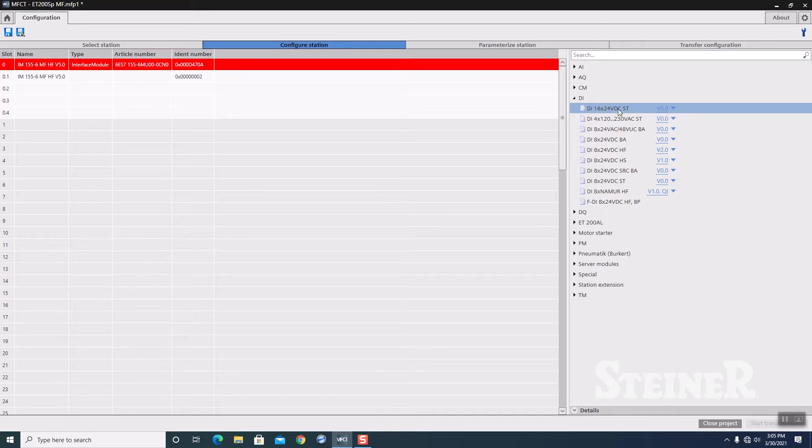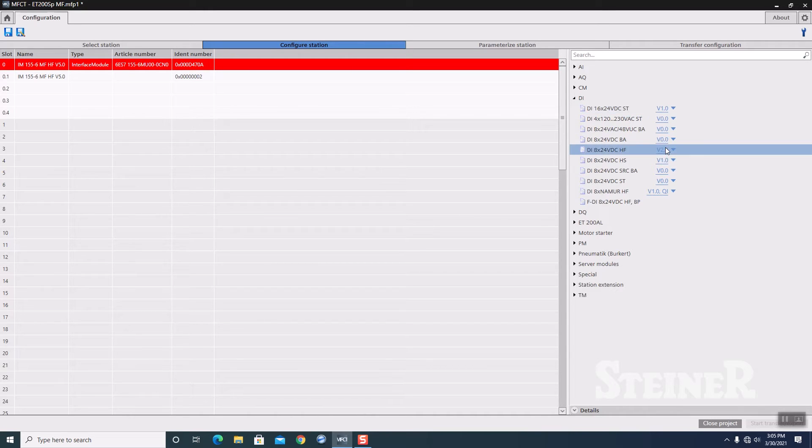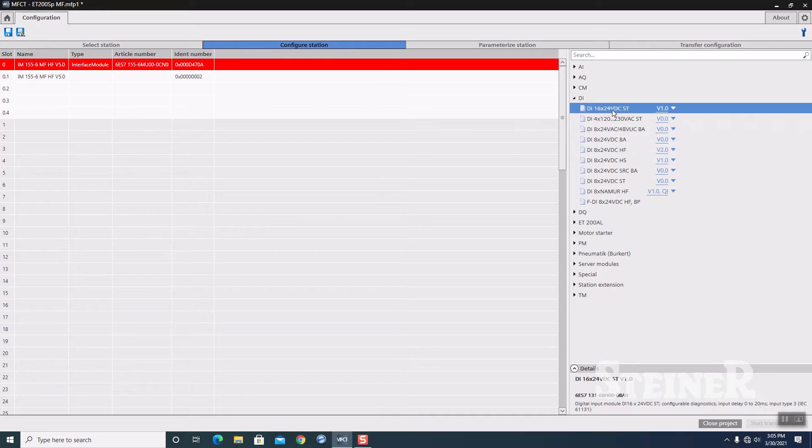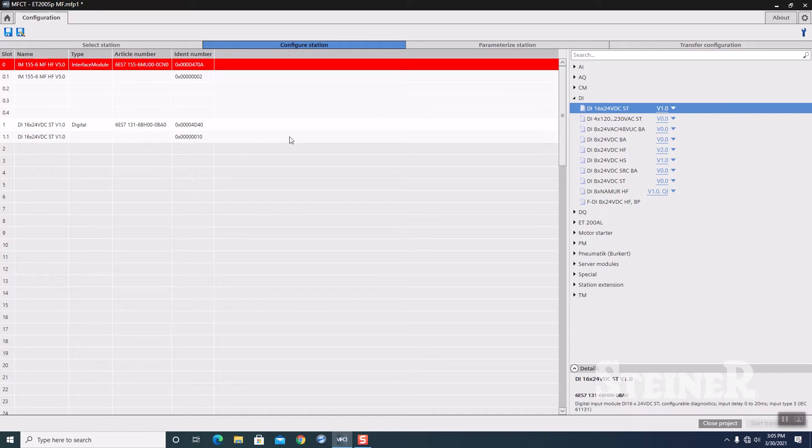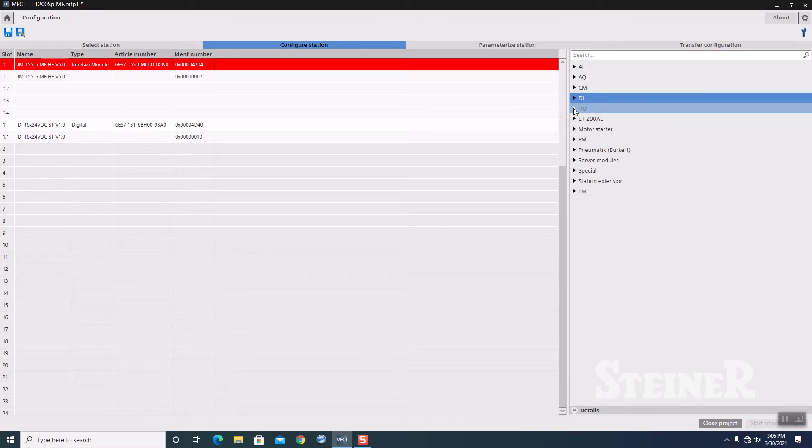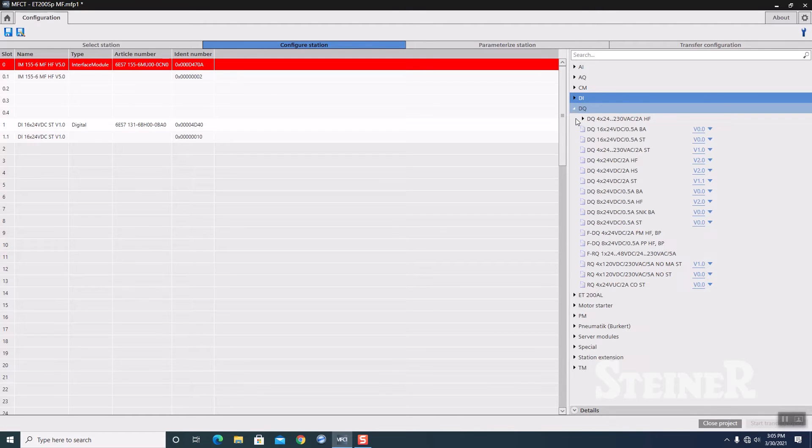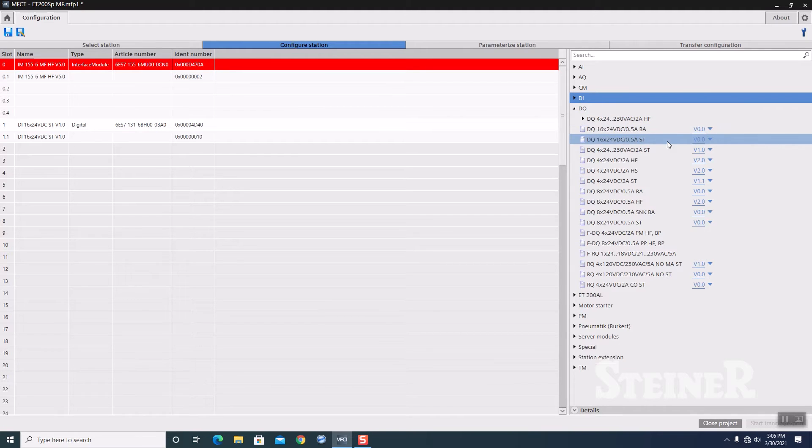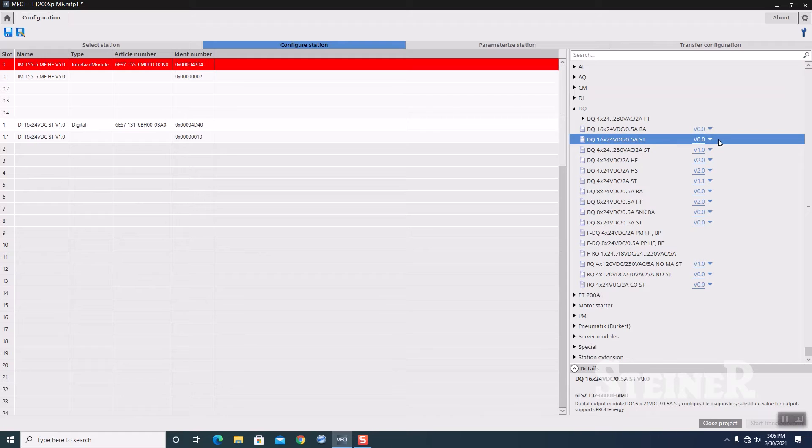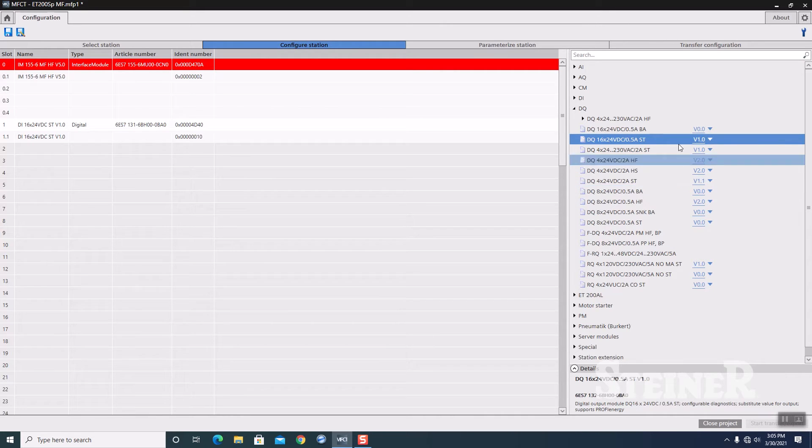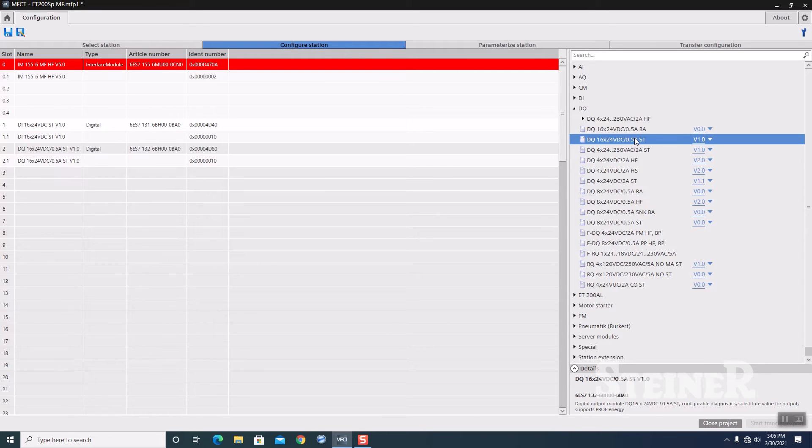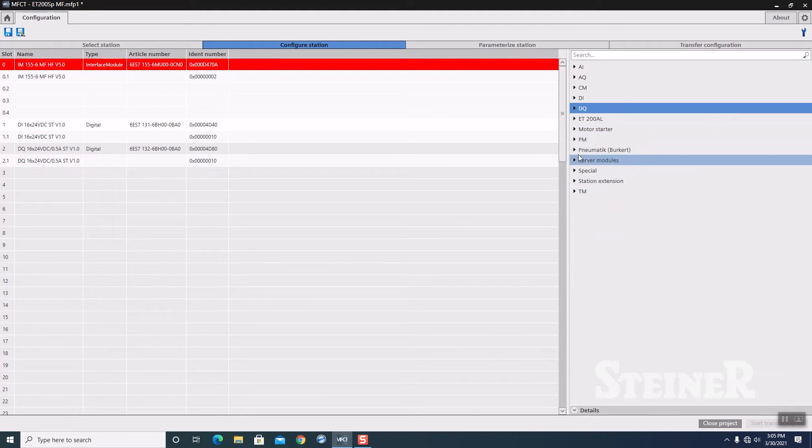I'm going to highlight my digital input. It's a 16-point 24-volt DC standard using firmware version 1.0. I'm going to double-click on that. It drops that into slot 1 for us. Then I'm going to select my output module, and that is also a 16-point. It's a ST for standard, and it has version 1.0. I'm going to double-click on it. That drops that into slot 2.